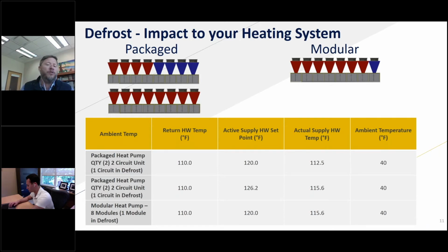If you go to fewer, bigger packages, then we have to think about things like, if I need 2 heat pumps for my system, I might need to use 3 heat pumps, because I have to overcome the fact that one of them is going to be in defrost. I have to run those other 2 to overcome that. And so that's kind of what you're seeing on that second row.